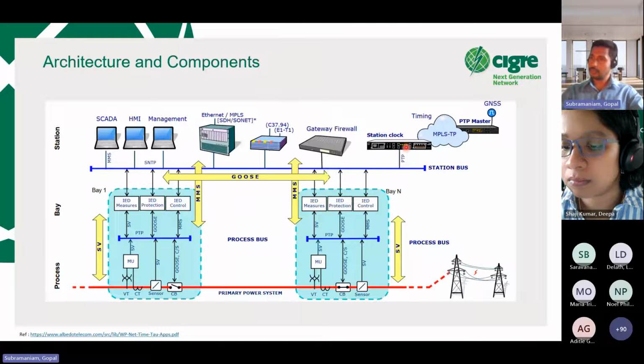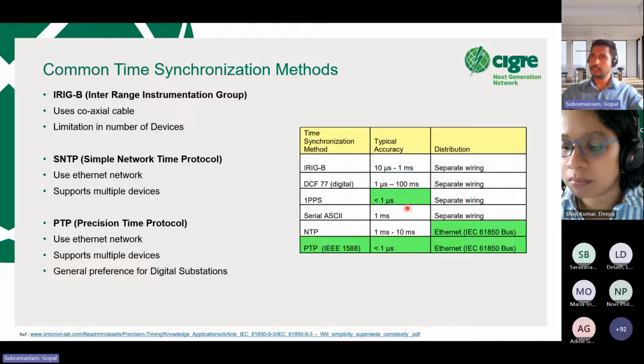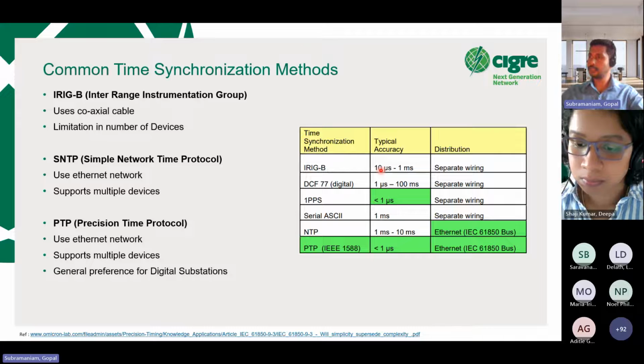Generally, for a common substation automation system, we'll be going with SNTP, simple network time protocol. But for a substation with a process bus, for high accuracy, we'll be going with precision time protocol. This is again an overview of different time synchronization methods. You can also see the accuracy of different time synchronization methods. So this is about IRIG-B. It has an accuracy of 10 microseconds to 1 millisecond.